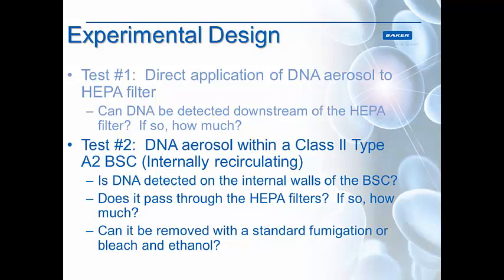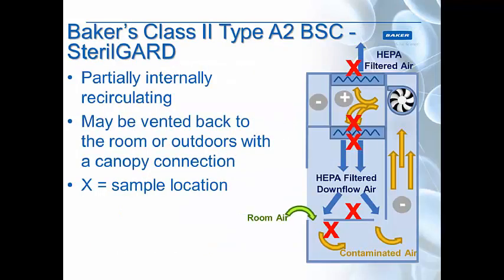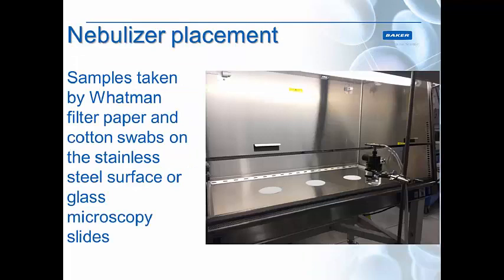For test 2, we put DNA inside a recirculating Type A2 cabinet. We used the Baker's Class 2 Type A2 biosafety cabinet — the SterilGARD. This is a partially internally recirculating cabinet, and the sample locations shown with red X marks were on the work surface, below the work surface, upstream and downstream of the supply HEPA filter, and downstream of the exhaust HEPA filter. This way we can see exactly where the DNA is landing and how much is getting through the HEPA filters.